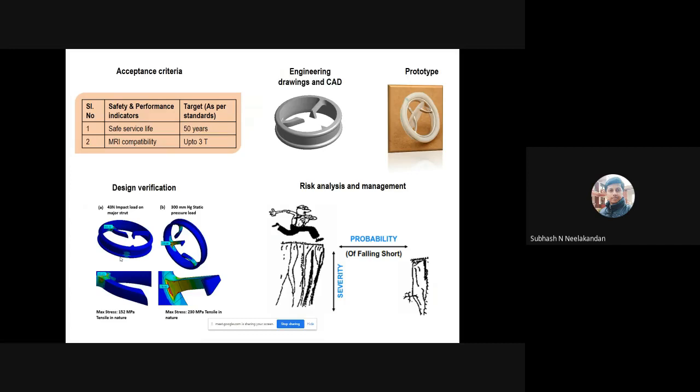To give an idea about the depth of testing involved in various devices, a medical device like a stent has only one critical component, basically a bare metal platform. A heart valve has three critical components. I am repeating, critical components, not the number of components.